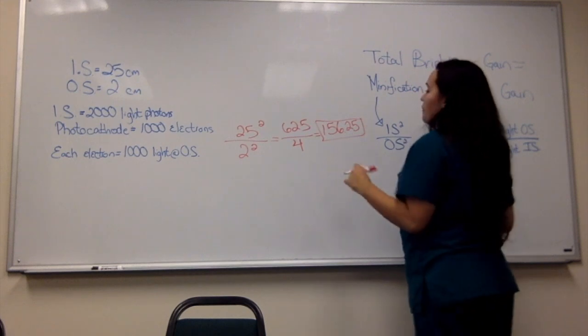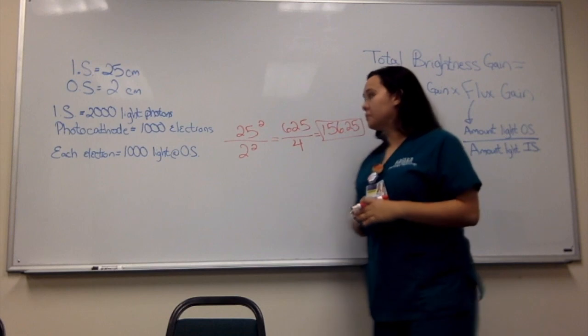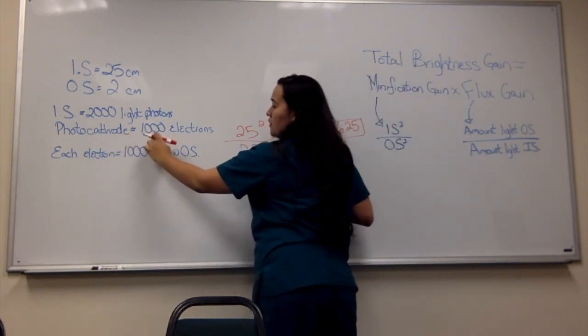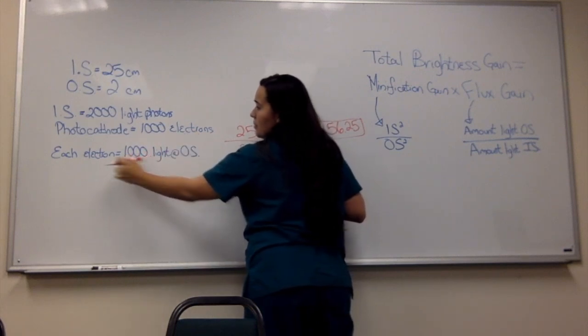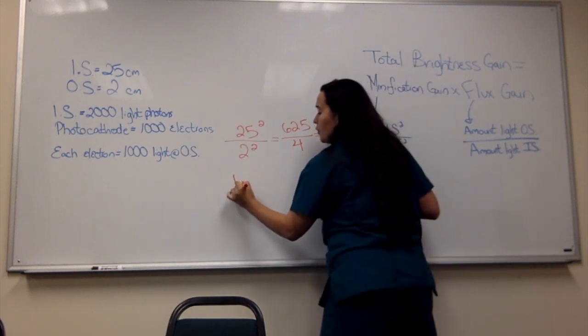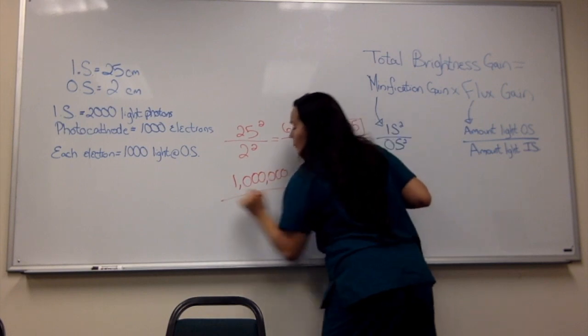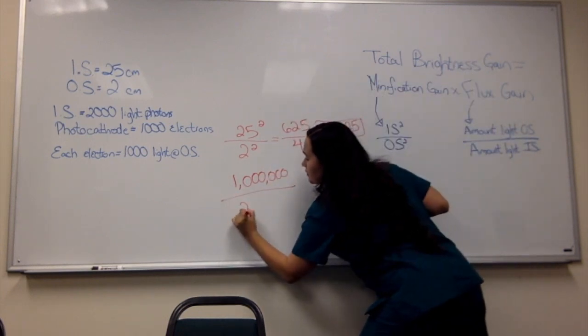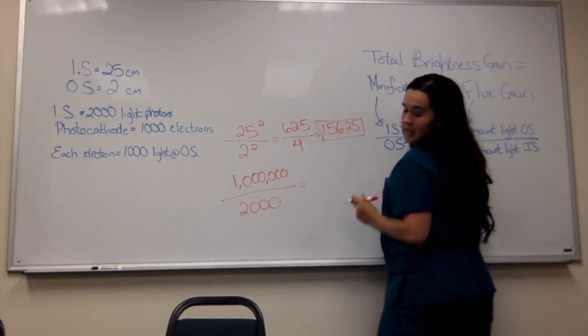Then I'm going to go over to the flux gain. For the flux gain, I need to find out how much light is given at the output screen. In order to do that, I need to look at the photocathode, which gives 1,000 electrons, and multiply by 1,000 because each electron gives out 1,000 light photons. So when you multiply that, that's going to give you 1 million. And I'm going to divide that by the amount of light at the input screen. When I do the math on that, it's going to give me 500.